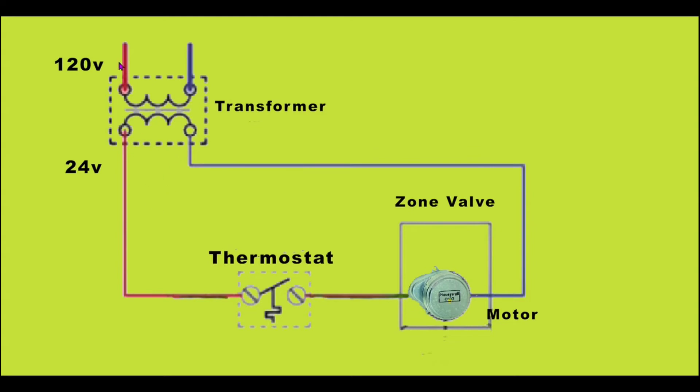So again, we have 120 volts coming in, 24 volts coming out. The thermostat is controlling the current to this motor which has two wires being connected: one to the thermostat and back up to the transformer.